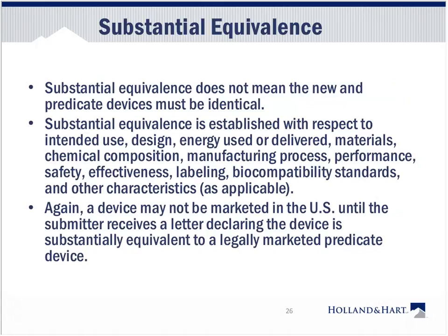Now, substantial equivalence does not mean the new and predicate devices are identical. Substantial equivalence is established with respect to intended use, design, energy used or delivered, materials, chemical composition, manufacturing process, performance, safety, effectiveness, labeling, biocompatibility, standards, and other characteristics as applicable. Again, there's no set rule from the FDA on this. Rather, you take a look at your product, you compare it to a predicate device, and then you make your case to the FDA as to why it is substantially equivalent and therefore should receive pre-market notification.